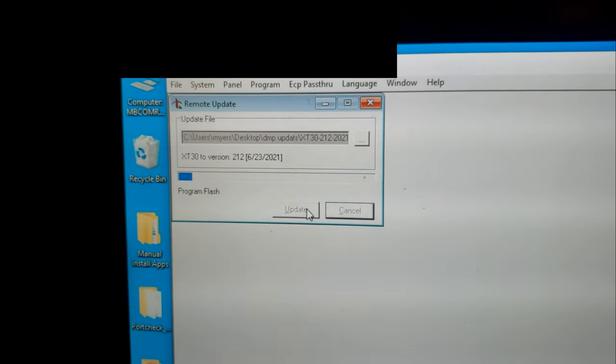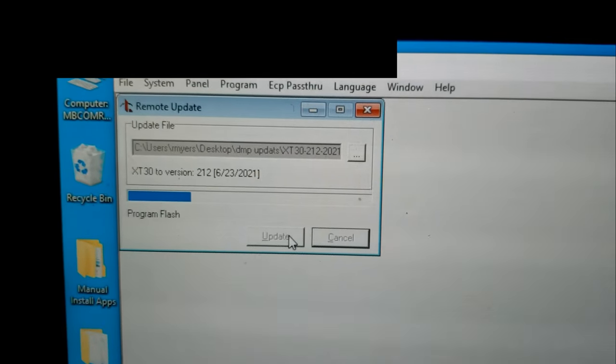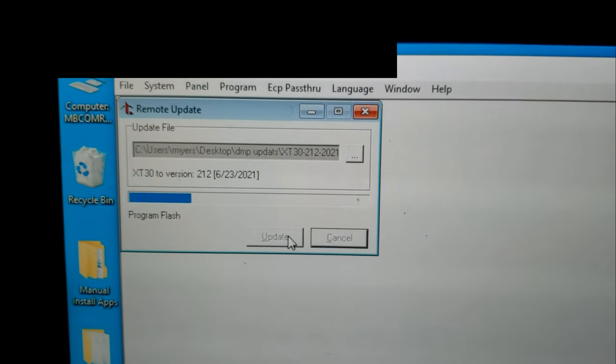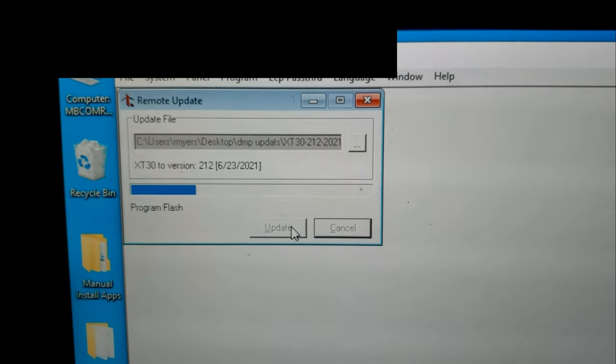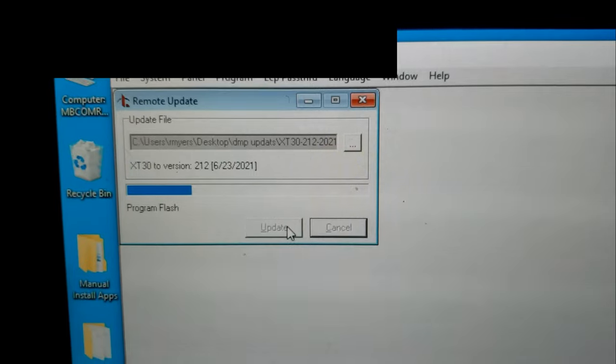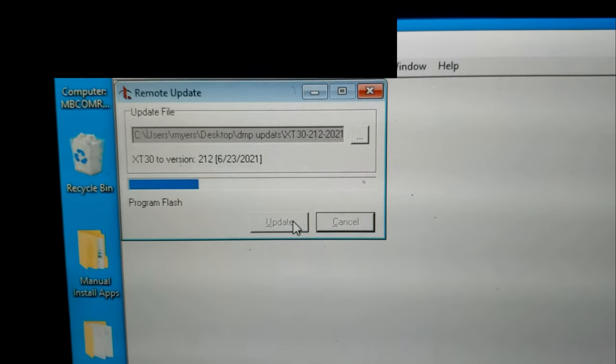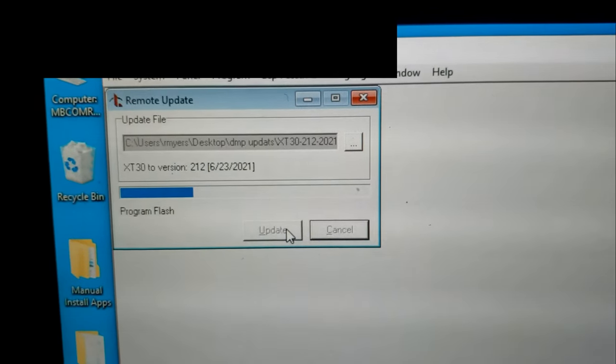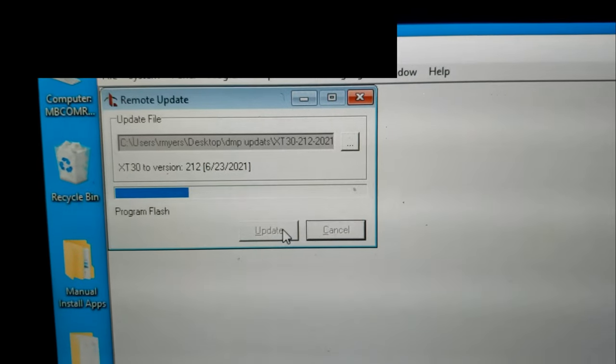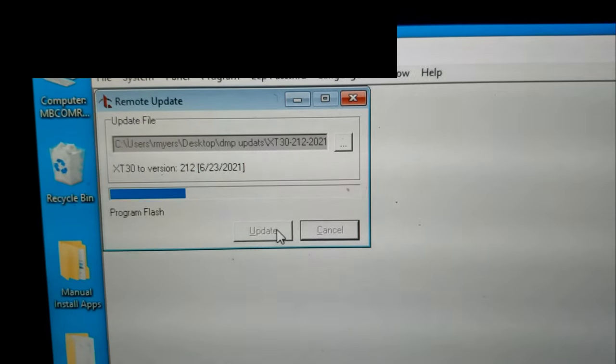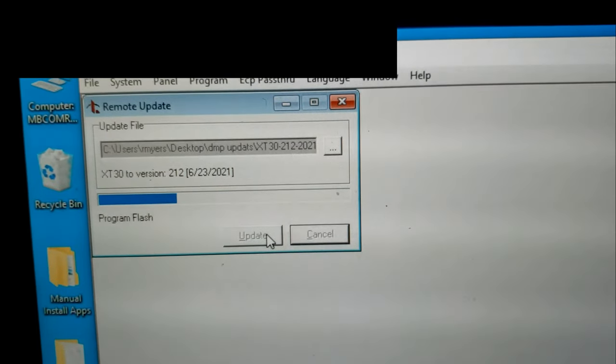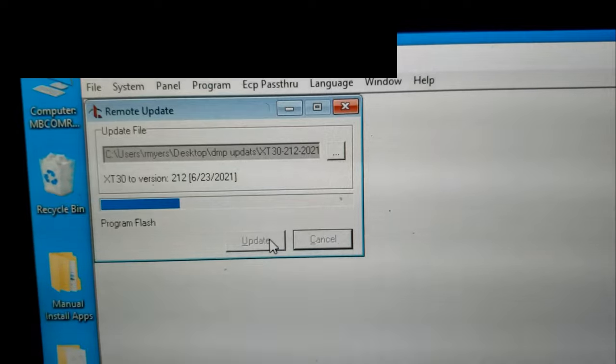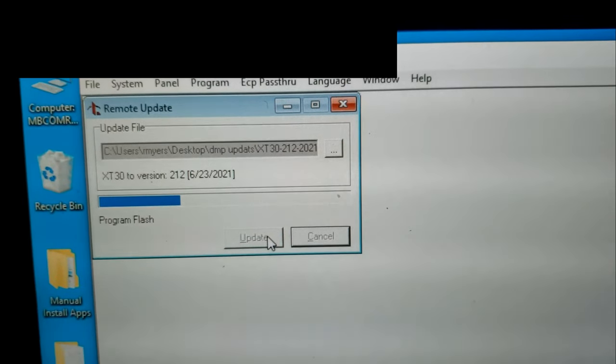All older cell cards—the firmware has to be updated before it'll take a new LTE cell card. So this must be done. Go to the latest version firmware off the DMP site before you upgrade the cell card, and make sure you power the panel down before you swap the cell card.